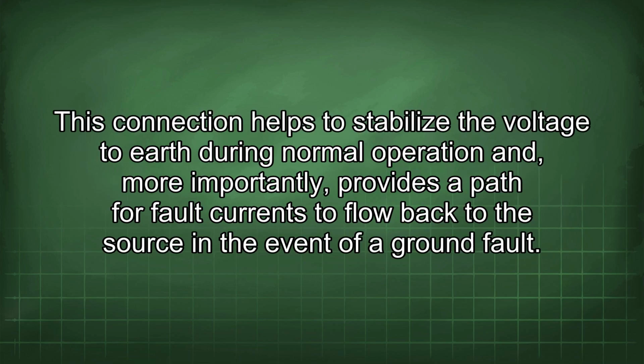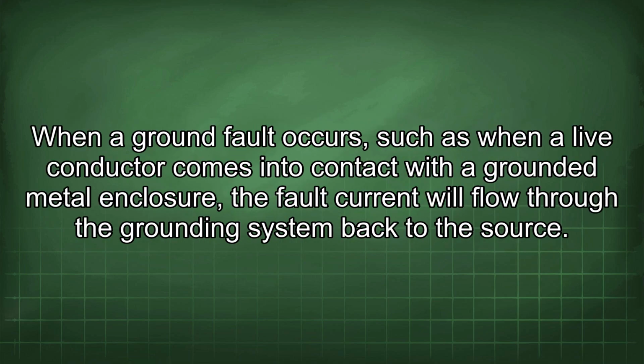This connection helps to stabilize the voltage to earth during normal operation and, more importantly, provides a path for fault currents to flow back to the source in the event of a ground fault. When a ground fault occurs, such as when a live conductor comes into contact with a grounded metal enclosure, the fault current will flow through the grounding system back to the source.